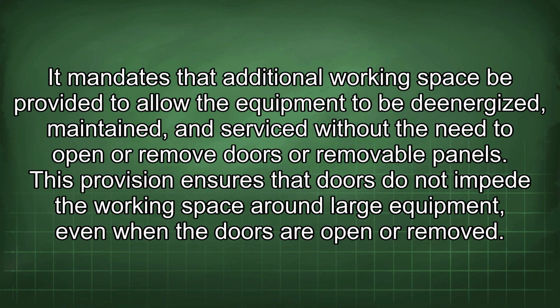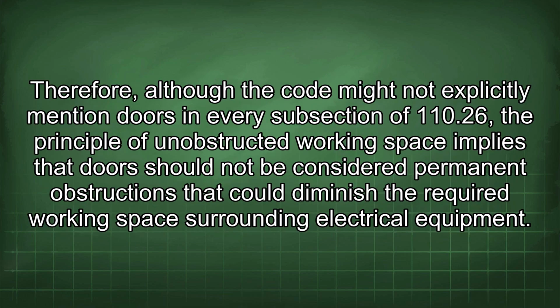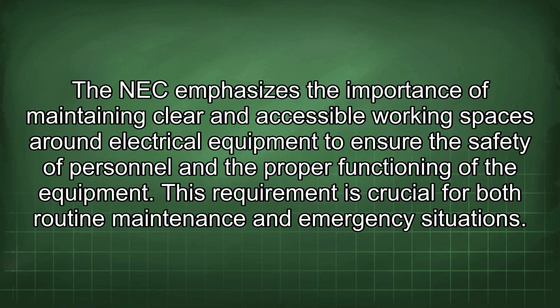or removed. Therefore, although the code might not explicitly mention doors in every subsection of 110.26, the principle of an unobstructed working space implies that doors should not be considered permanent obstructions that could diminish the required working space surrounding electrical equipment. The NEC emphasizes the importance of maintaining clear and accessible working spaces around electrical equipment to ensure the safety of personnel and the proper functioning of the equipment.